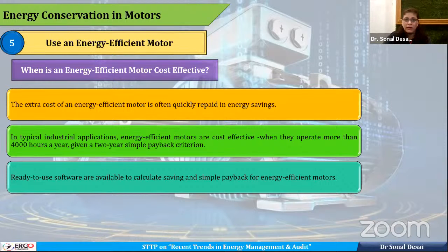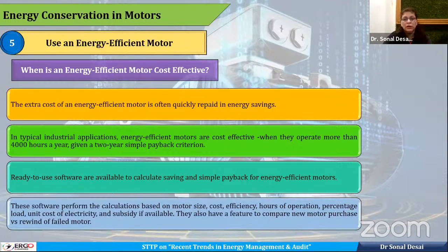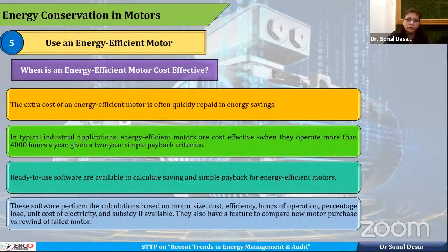There are ready-to-use software tools available which suggest whether we should adopt the energy efficient motor or the standard one. They consider hours of operation, percentage load at which the motor is operating, cost of electricity, what subsidy is available, or what the salvage cost of the old motor is. Based on these, the software can suggest which to choose.